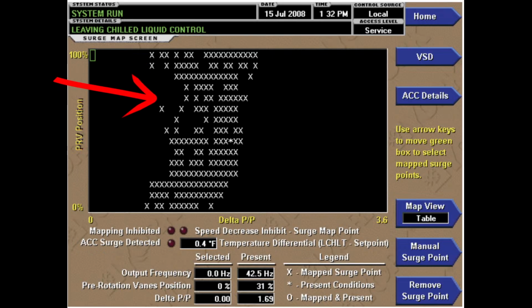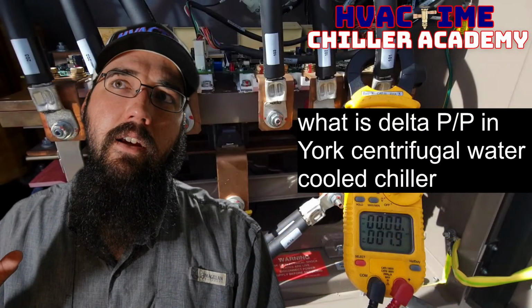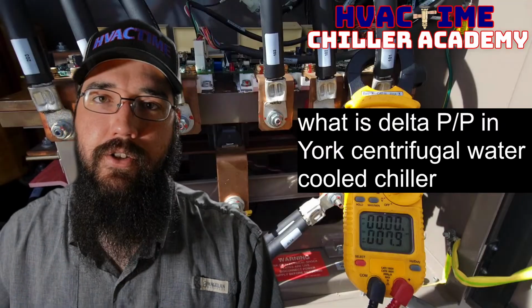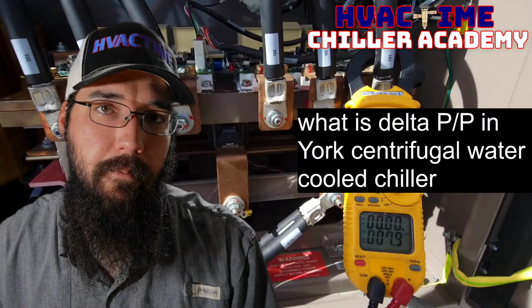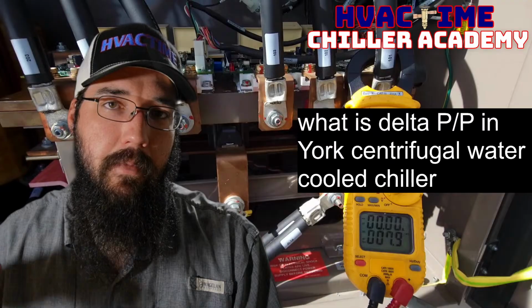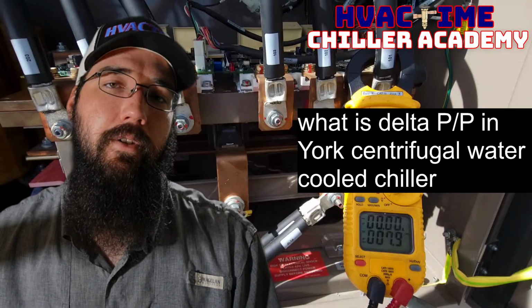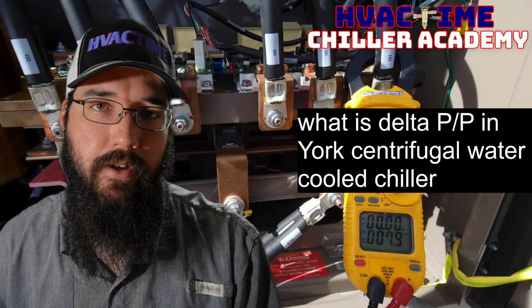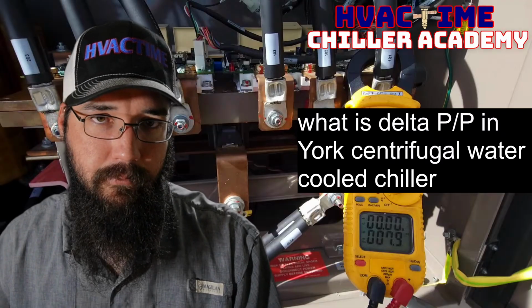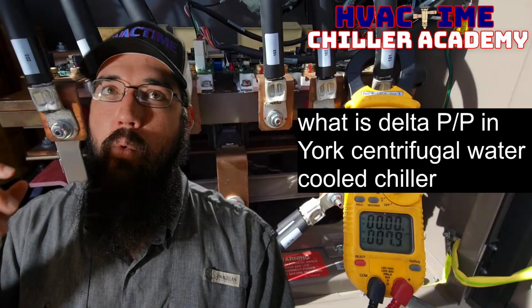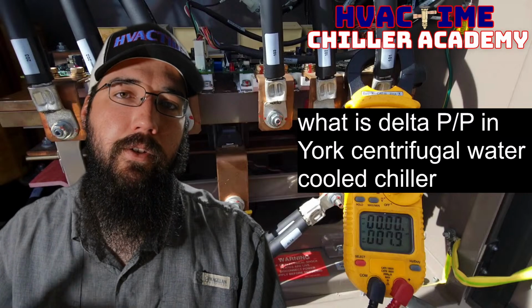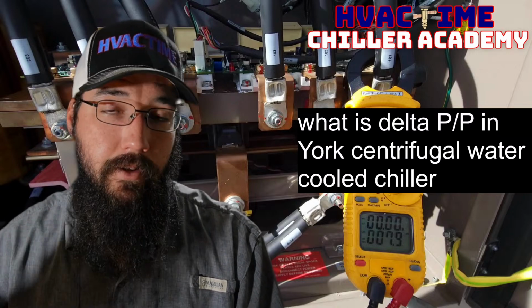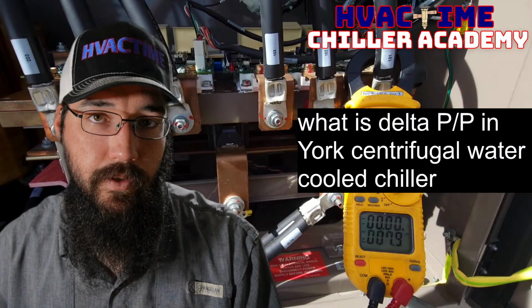I'll give a prime example. If the condenser water pump had an issue, or you had a strainer issue, or you needed a PM, that's going to start causing major head pressure increases because of whatever happened on the condenser water side. Pick a symptom or a problem. One of the symptoms is you're going to increase head pressure, you're going to increase lift, and you're going to deal with a lot more surging at that point.